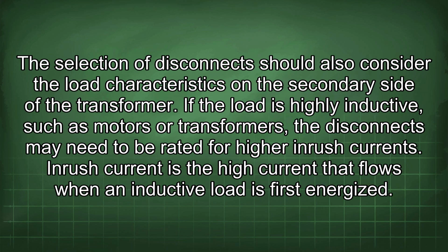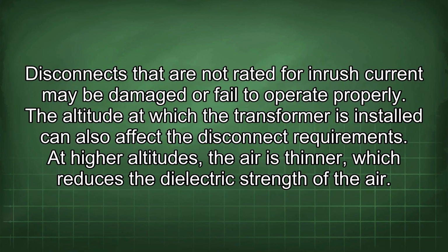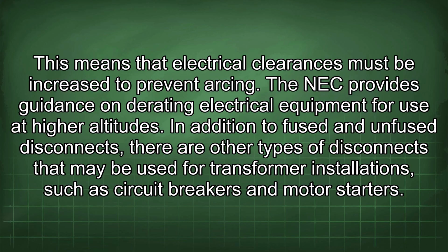The selection of disconnects should also consider the load characteristics on the secondary side of the transformer. If the load is highly inductive, such as motors or transformers, the disconnects may need to be rated for higher inrush currents. Inrush current is the high current that flows when an inductive load is first energized. Disconnects that are not rated for inrush current may be damaged or fail to operate properly. The altitude at which the transformer is installed can also affect the disconnect requirements. At higher altitudes, the air is thinner, which reduces the dielectric strength of the air. This means that electrical clearances must be increased to prevent arcing. The NEC provides guidance on derating electrical equipment for use at higher altitudes.